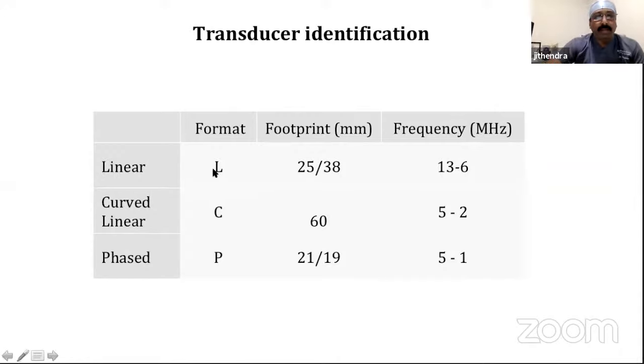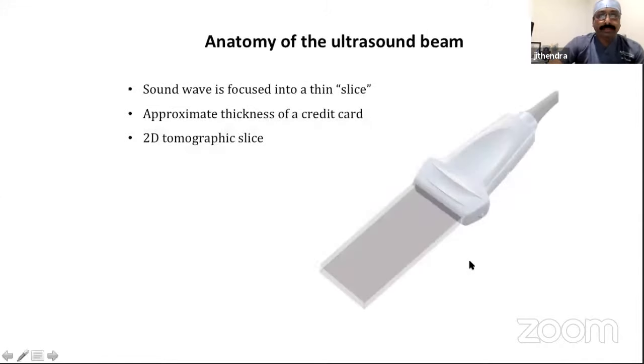Now, how do you identify the transducer among all the probes? The linear probe is commonly labeled L. The footprint is somewhere between 25 to 38 millimeters. The pediatric probe has a footprint of around 25 millimeters, whereas the frequency ranges from 6 to 13 megahertz, and some transducers go even higher, above 15. A curvilinear probe is usually labeled C, and the footprint is around 60 millimeters, that curved probe you've seen, and the frequency is 2 to 5 megahertz. For phased array probes, the footprint ranges from 19 to 21 millimeters, and the frequency used is between 1 to 5 megahertz.